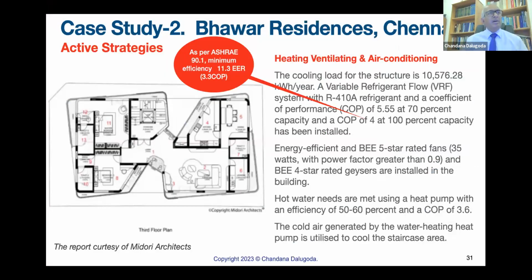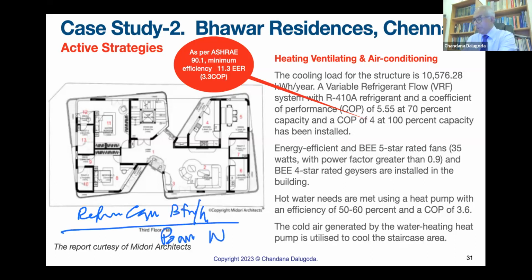We don't call it kilowatt per ton here. It is EER. So EER is the efficiency found this way: refrigeration capacity in BTU per hour divided by power input in watts. BTU over watts is EER. So what we say is, the EER of equipment should be equal to or higher than 11.3, or COP, for that matter, 3.3. COP is also efficiency, so this is used for COP.